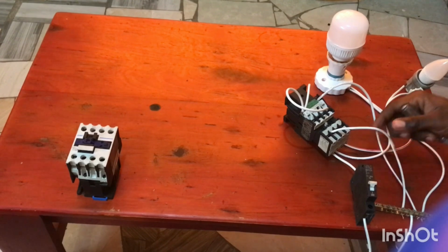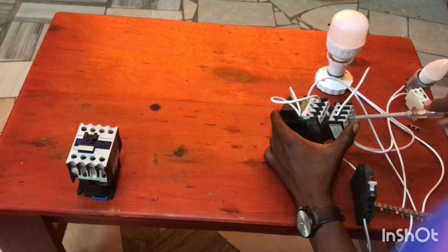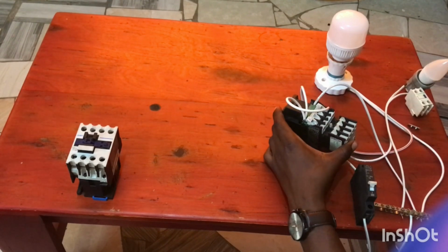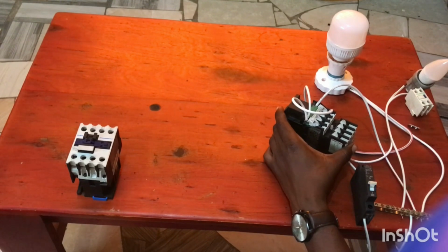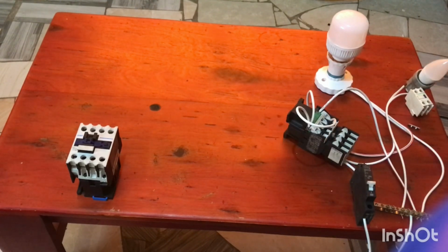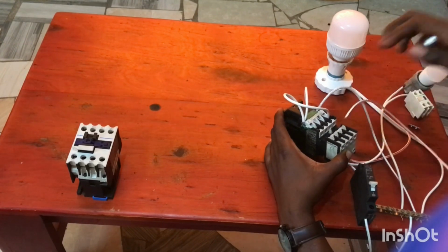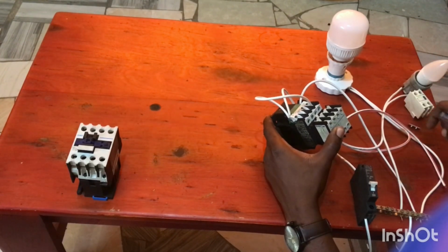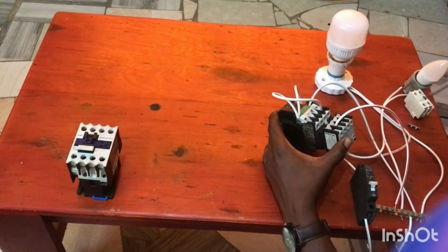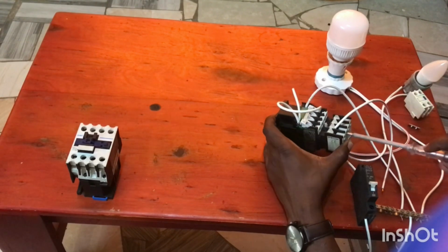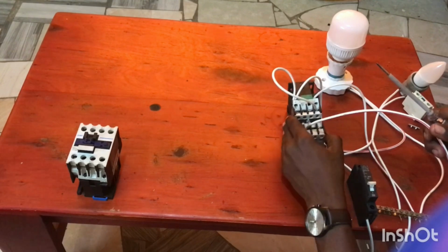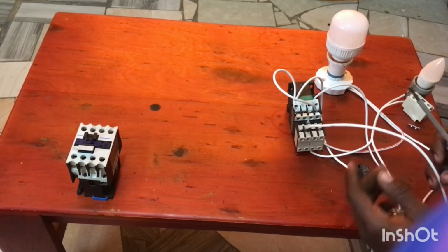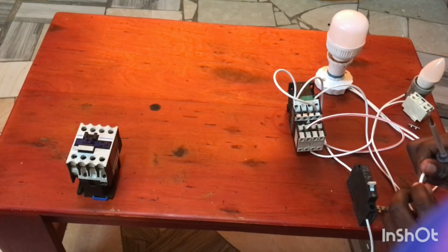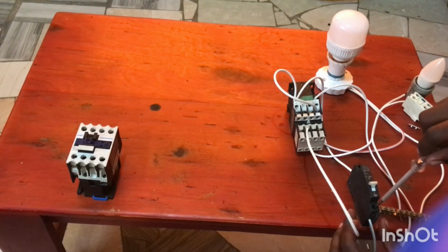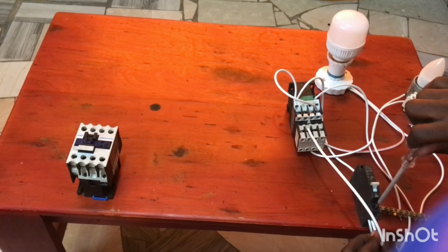So here the light cannot go on unless we get the power from the source. The inlet power should be from the source. So I'm going to get power from the source and put it at a normally closed contact. So the inlet of the normally closed contact, then we put it at the source. This one is direct, it will not go to the circuit breaker. So we expect this light to be on even though the contactor is not energized. That's the normal way of doing it.